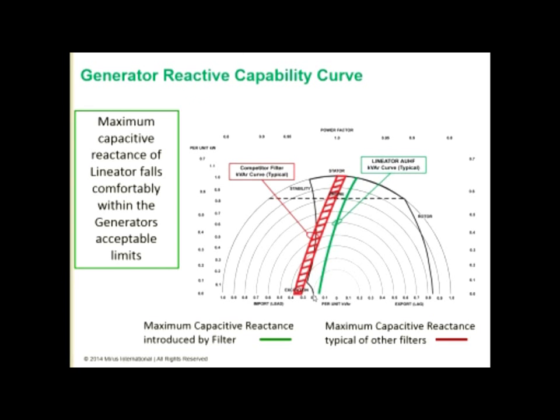In this case, on the y-axis, we've got your load in kilowatts of the generator. On the x-axis, we've got the percent of reactive power, leading on the left side, lagging on the right side. And the diagonal lines are the load power factor lines. And here, if we look at 0.9 load power factor at 80% load level, that would indicate a 40% reactive power component. So that's how we can read these charts that are provided by all generator manufacturers.